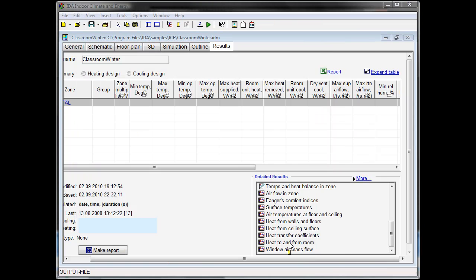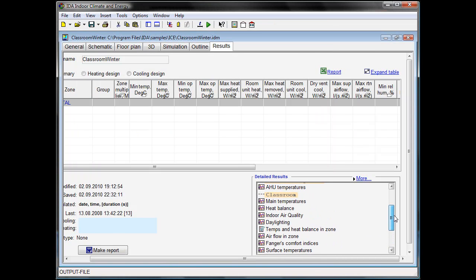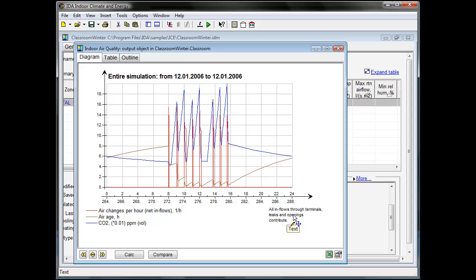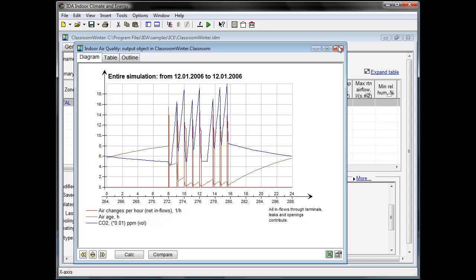Looking at the air quality report, this time for a whole weekday, we can verify that the opening times are long enough to guarantee the air quality. In blue we can see CO2 concentration going up during the lessons and down during the breaks.